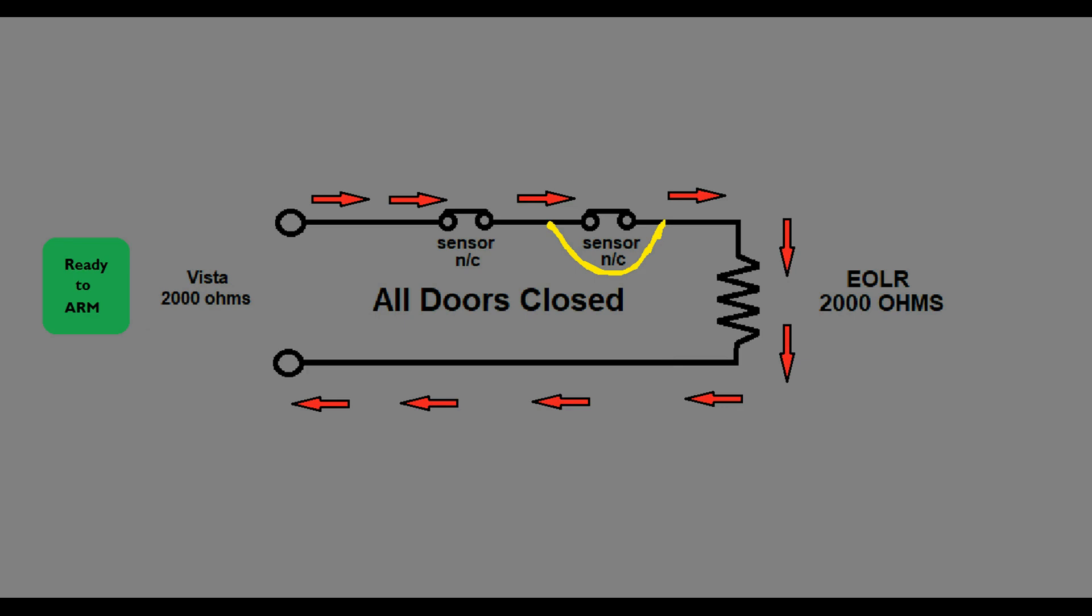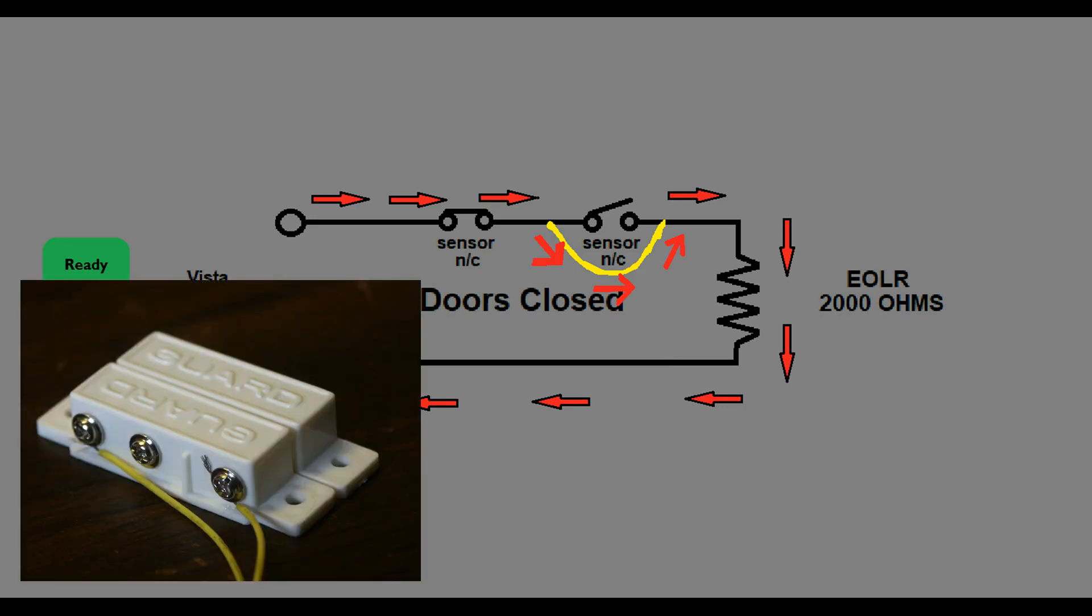However, what if there's a short across one of your sensors? When the sensor opens, the current simply goes around the short and continues on like normal. The alarm panel will not see the open sensor. So, with this information in mind, it would probably be wise to ensure that when you install a sensor, the electrical contacts are not accessible to the general public.